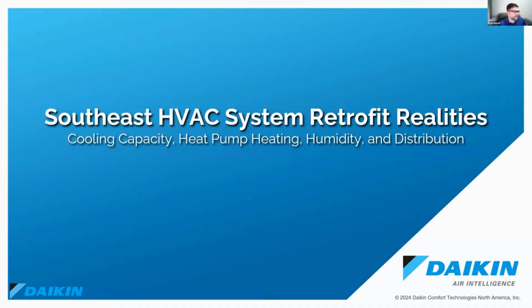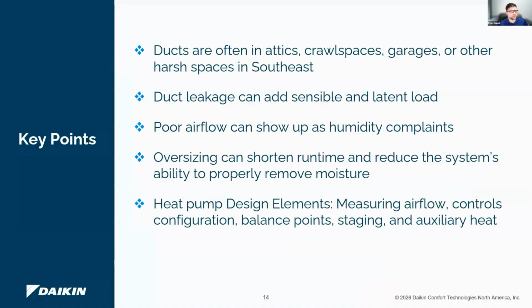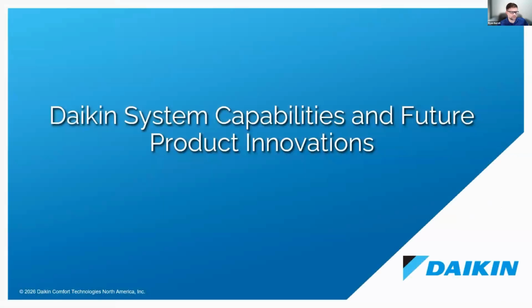Southeast HVAC system retrofit realities: cooling capacity, heat pump heating, humidity distribution. That's what we're really focused on. We're really focused on, obviously, controlling moisture in and out of the home. So, key points: ducts are often in attics and crawl spaces, literally the worst places you could ever want them. Duct leakage adds sensible and latent load. Poor airflow can show up as humidity complaints. Oversizing and all those installation faults end up compounding.